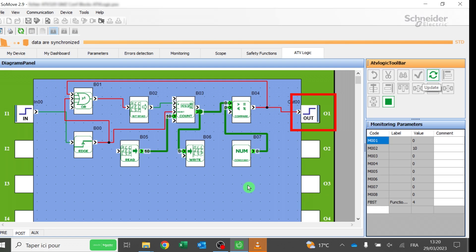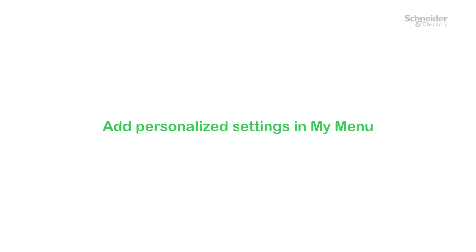When DI1 is activated, the output of the count function block is set to 1 and drives the virtual output 01 assigned to FW order. Thus, the ATV320 starts. When the actual value reaches 0, the output of the count function block is set to 0 and stops the ATV320.